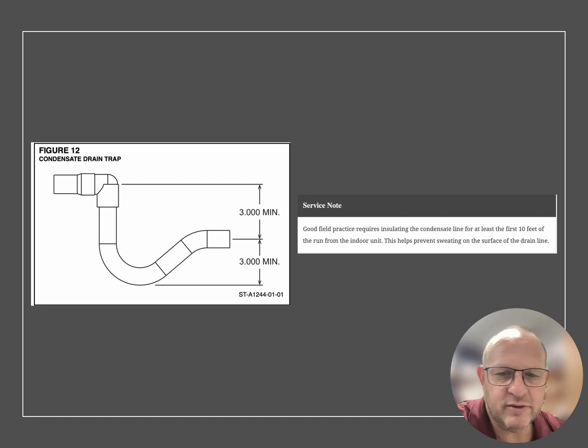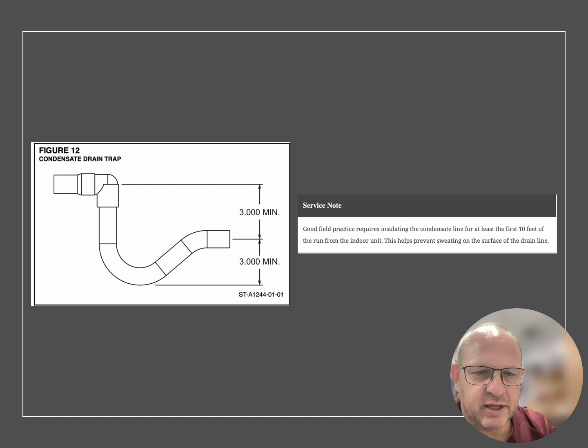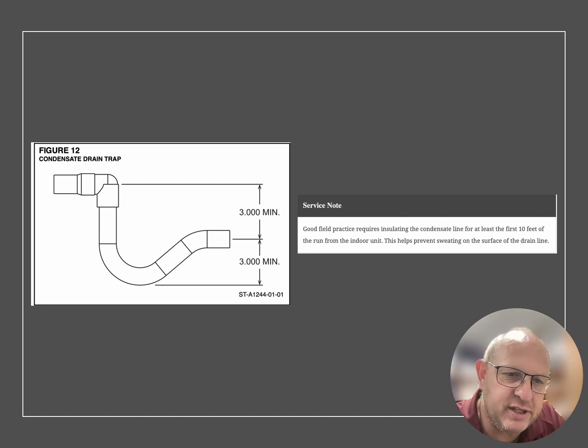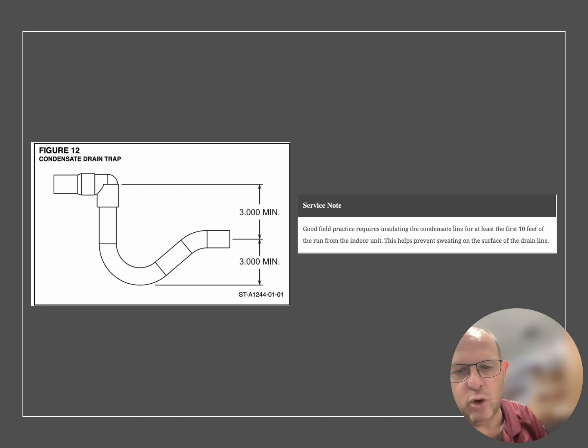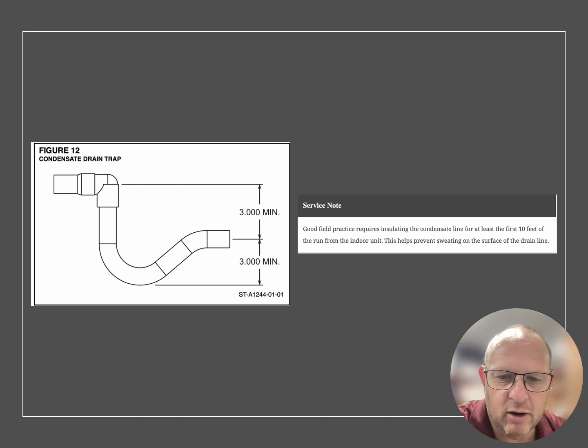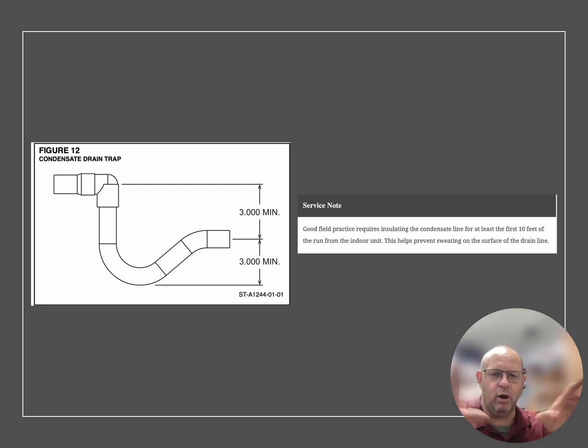There is a minimum trap depth that we want, and the purpose of this is we want to keep that water within the trap, especially on our air handling units. Our air handling units will actually suck air up through that line if it is trapped inappropriately. So 3-inch minimum trap from the outlet of the condensate of the indoor unit to give that enough area in there to hold that water, so we do not suck air up there. If we were to suck air up into the indoor unit, it would actually back the condensate up and it would overflow outside of the indoor unit, causing damage possibly to downstairs or to the environment that it's actually in.